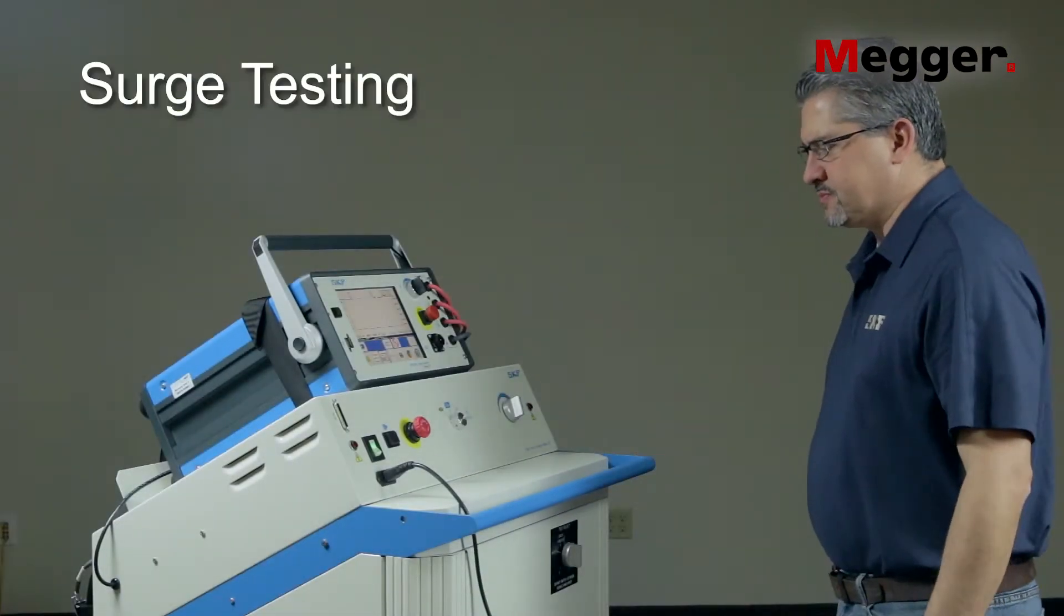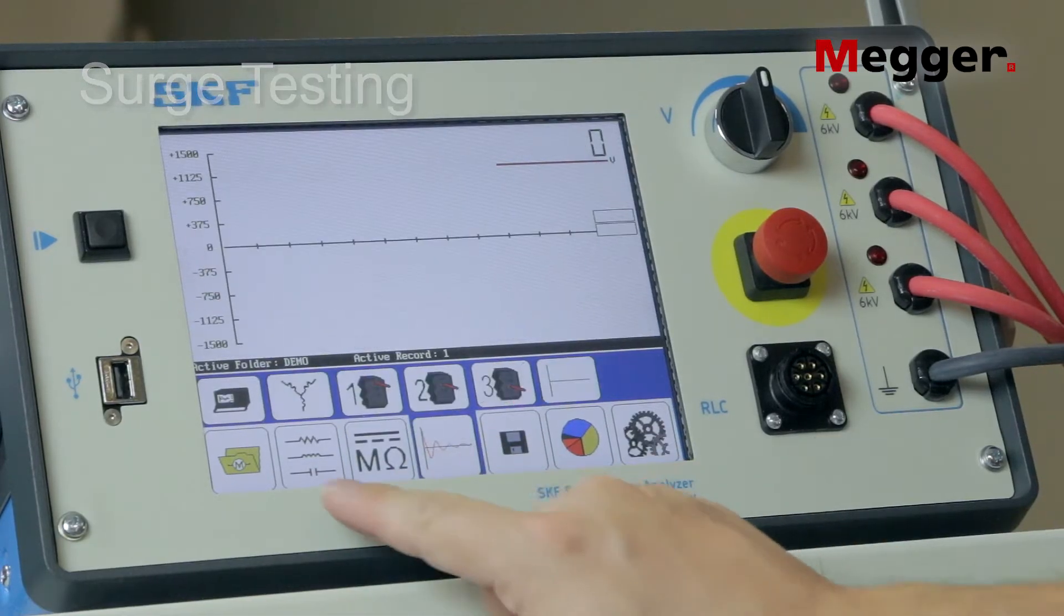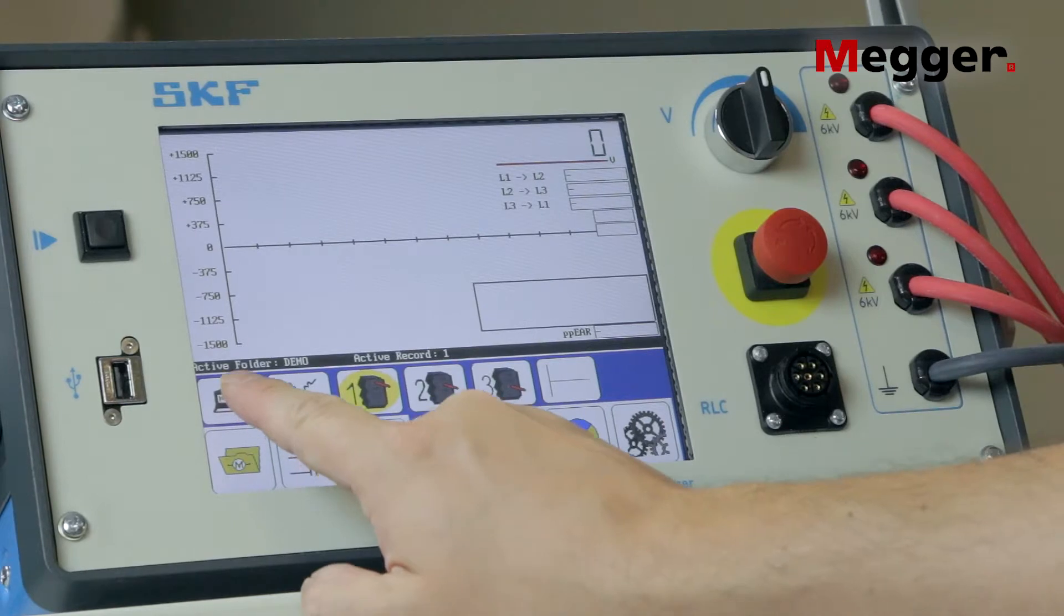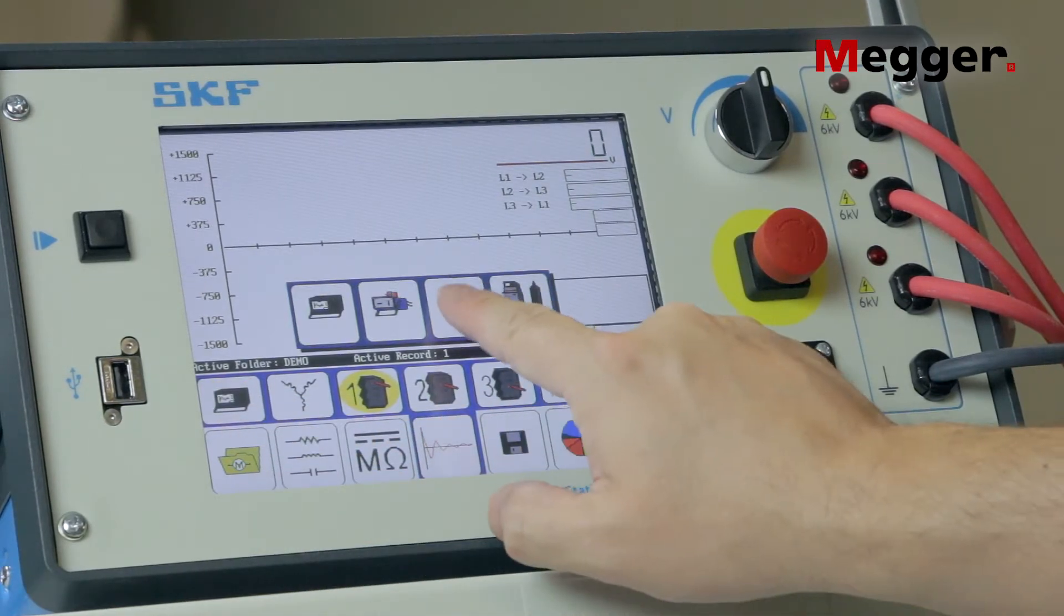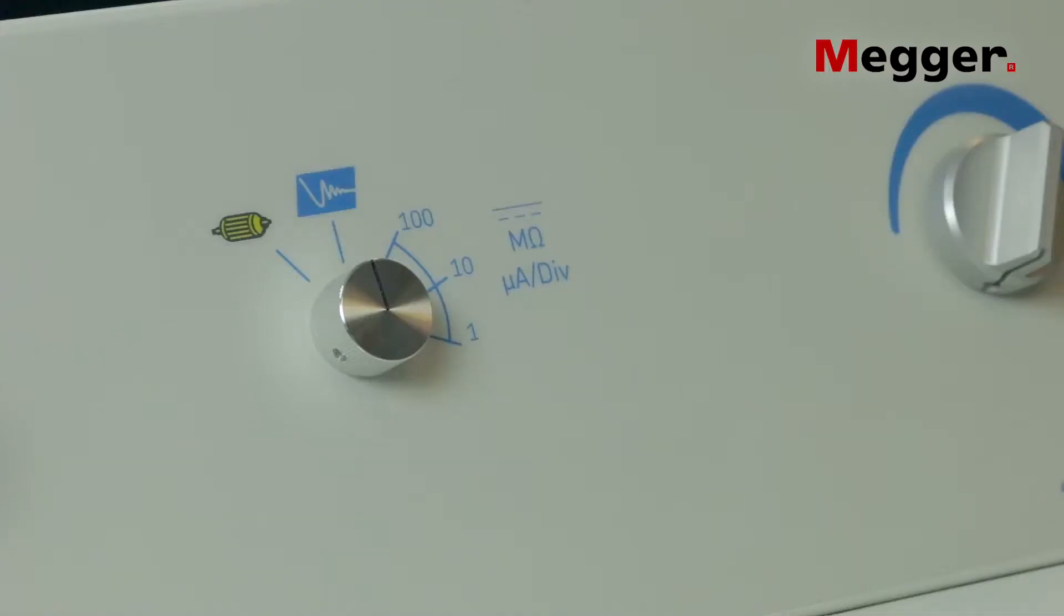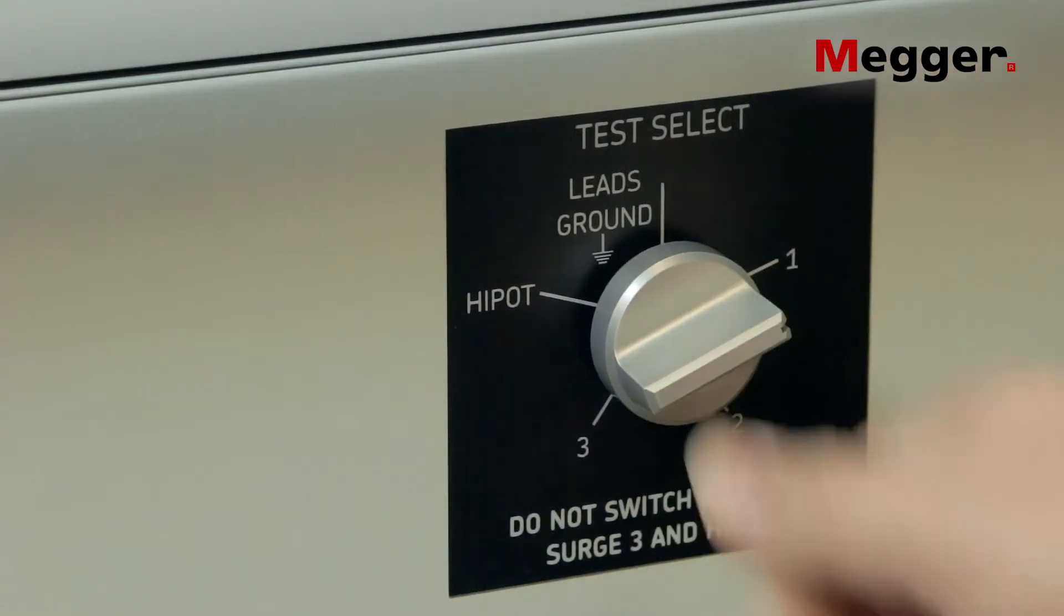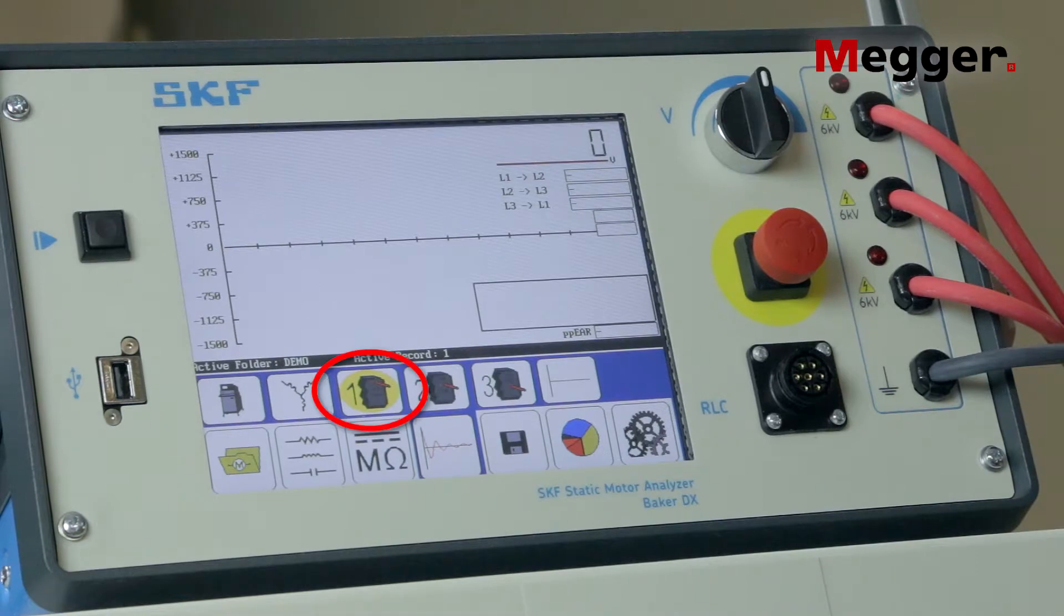Now we'll perform surge testing on this three-phase motor. On the main screen of the DX, select the surge test. Select the power pack. Verify that the voltage control knob is set to zero. Turn the power pack's function switch to the surge test position. Turn the test select knob to lead one and check that lead one is highlighted in yellow on the DX.